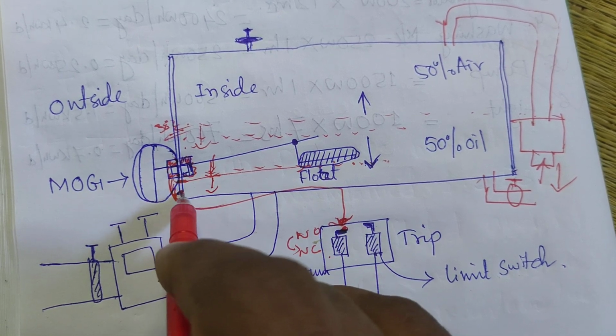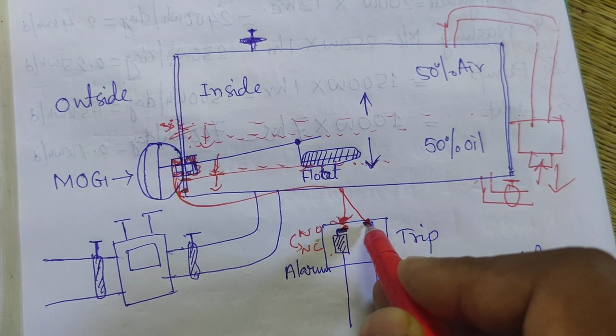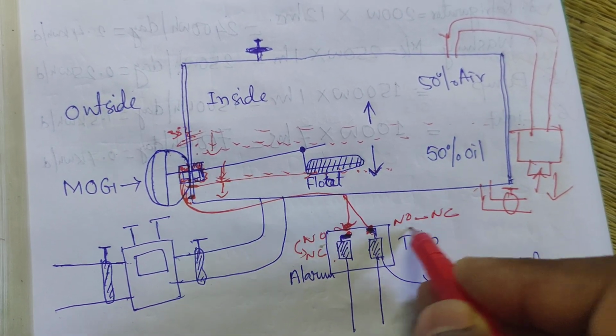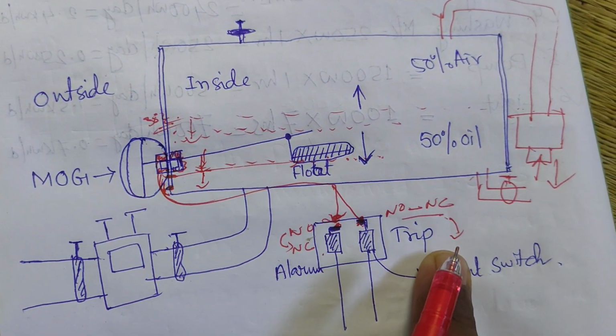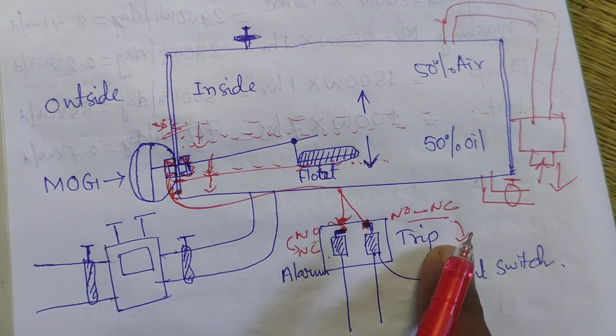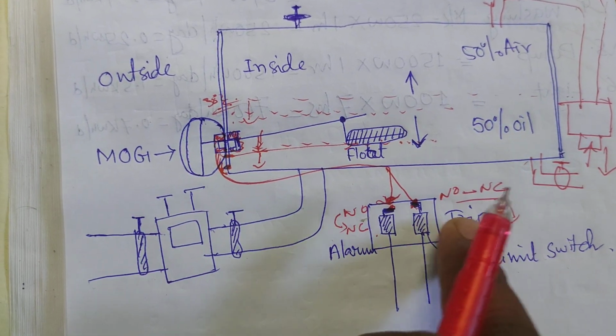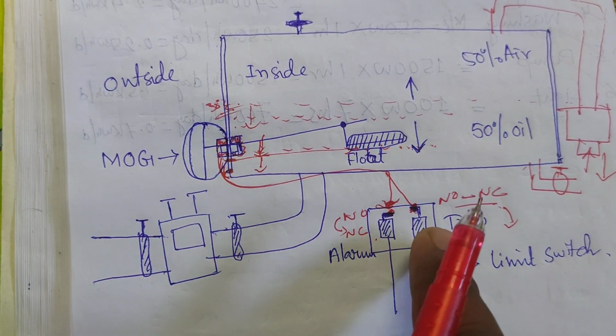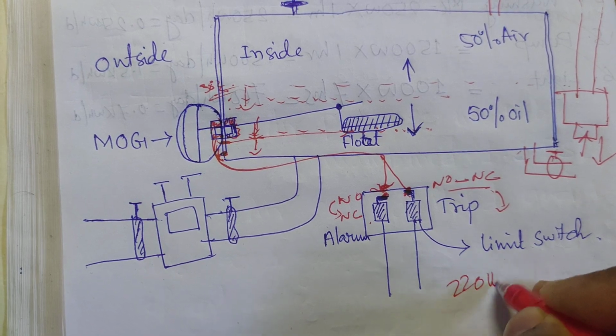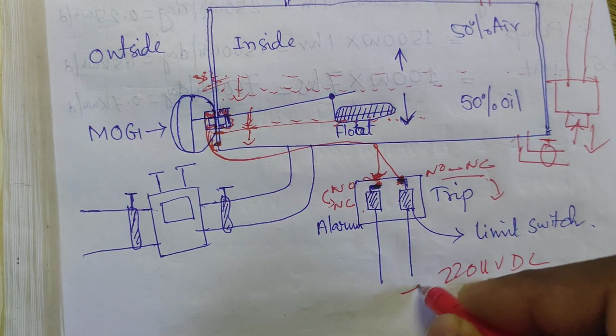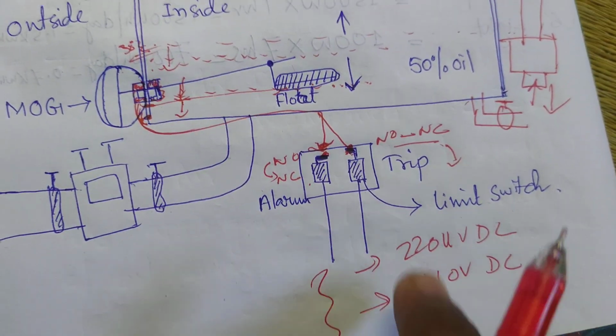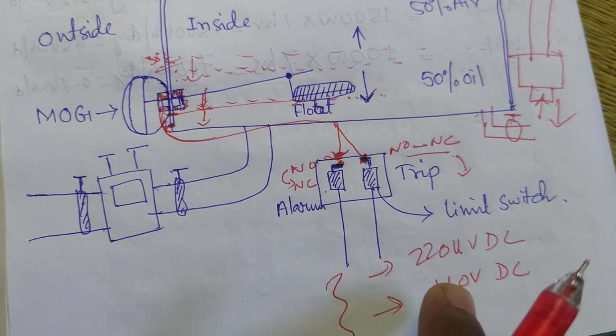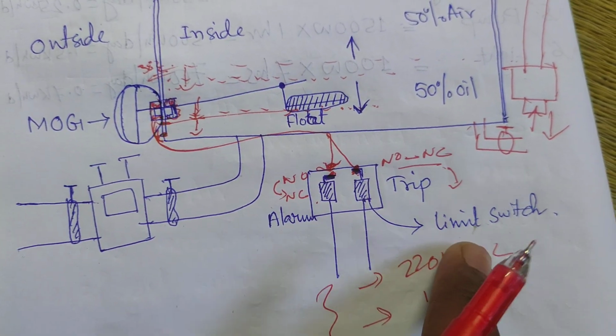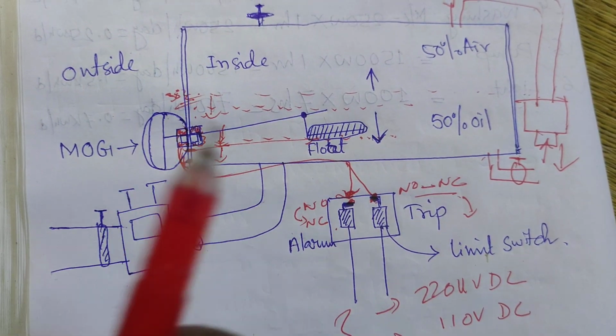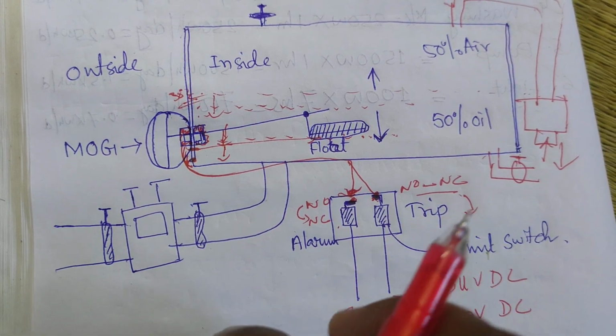If you are not taking care of the transformer, the oil level gets down again and the tripping position will be reached. Then this flange will pressurize this limit switch, and the limit switch will operate NO to NC, and this is directly connected with the circuit breaker tripping coil, and the tripping coil will get the pulse. After getting the pulse from this MOG contact, the direct DC, that means 220 volt DC or 110 volt DC as per your installation's DC power capacity, will go through the tripping coil of the circuit breaker, and the transformer will be isolated permanently. So this is the safety procedure of the transformer.